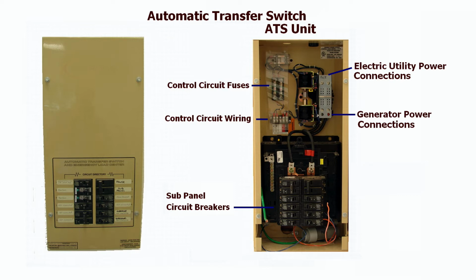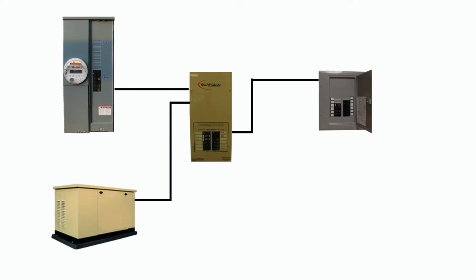In this case, we have a 100 amp sub panel which is built into this automatic transfer switch unit. And in this particular installation, we have another sub panel that will be attached to the transfer switch panel. So you've got a variety of circuits that are going to be powered up. The size of the generator will be the indicating factor of the amount of power that can actually be fed into the circuits that will be backed up by generator power.